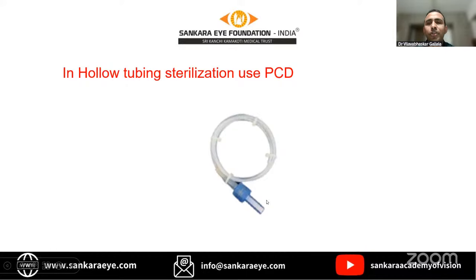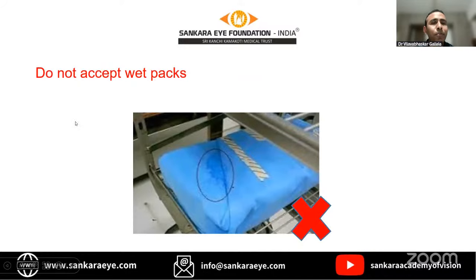So you need not use it in every load of these hollow instruments. In between, for confirmation's sake, you can use this PCD, process challenge device, intermittently. And one more important thing, once you receive these post-sterilized packs, make sure there is no wet moisture over these packs. This moisture can act as a vector for microorganisms during the transport process, during the time of storage, all these things.